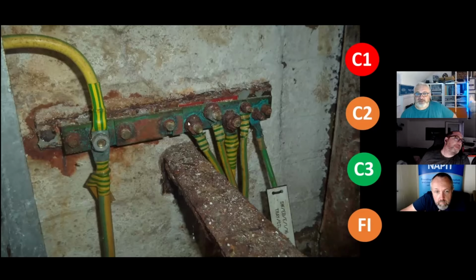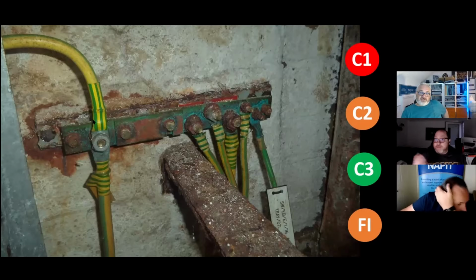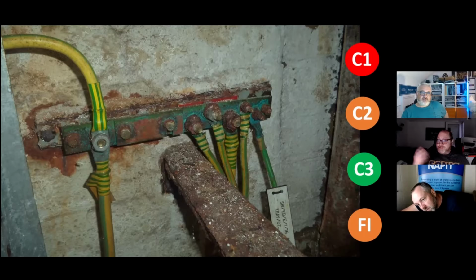And if you're the inspector, you've got a duty of diligence telling them it's going to fail. What you need to remember, specifically with earthing in particular, is when it does fail, it doesn't stop things operating, other than maybe the ability of hiding indirect neutral currents, potentially. So people might not get that immediate acknowledgement that something has failed in their system. They may not seek assistance when it fails.